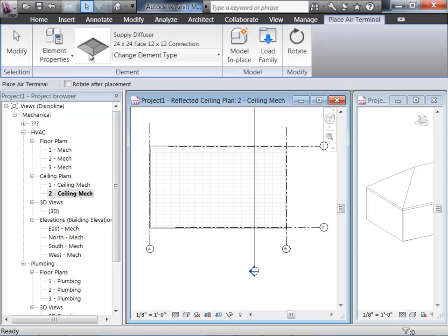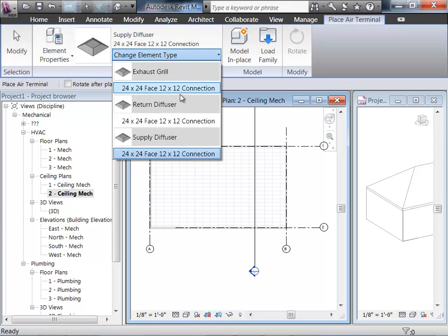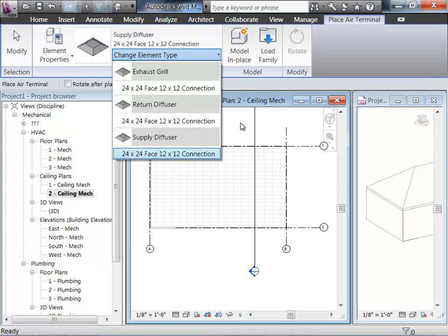If I go to the Home tab, Air Terminal, let's see what I have available. It looks like I have three types right now: the exhaust grill, a return diffuser, and a supply diffuser. None of these diffusers are hosted by anything else. So if I were to drag the supply and put it into this space, it's going to go directly to the work plane of that view — which by default is level 2 — so it's going to place this diffuser on the ground. What I want to do is load a diffuser that's hosted by an actual surface, so I can put it in the ceiling or on a wall.